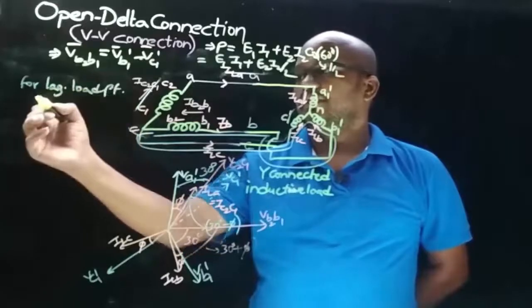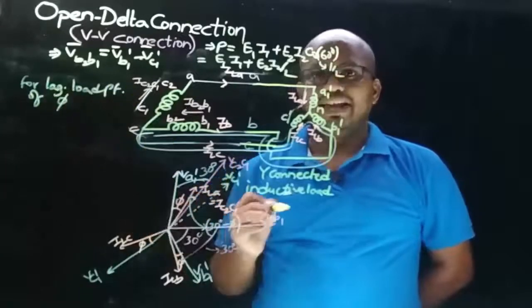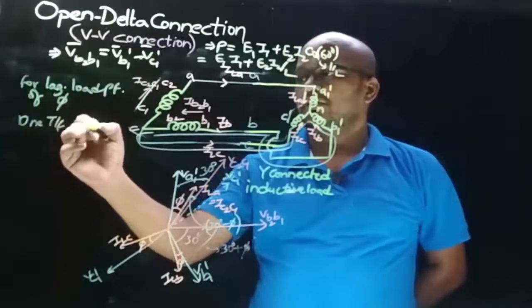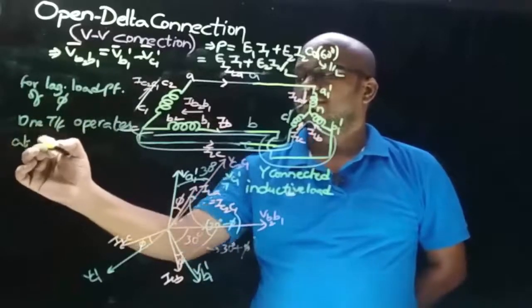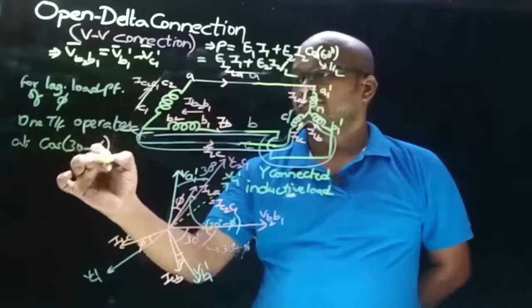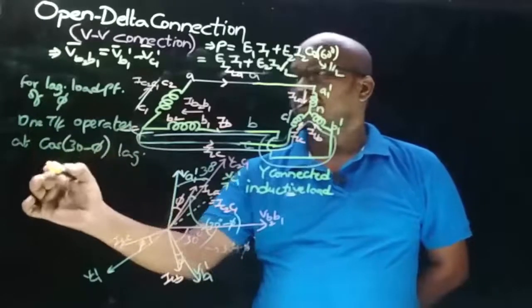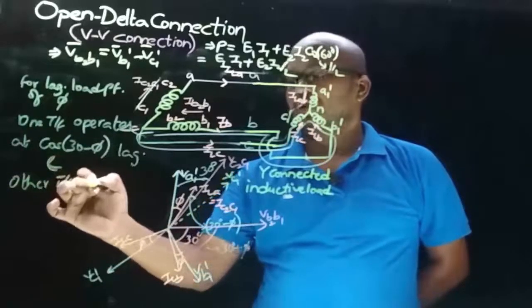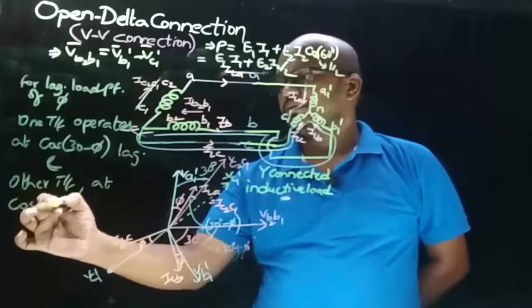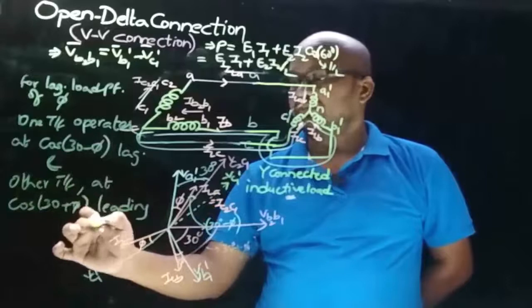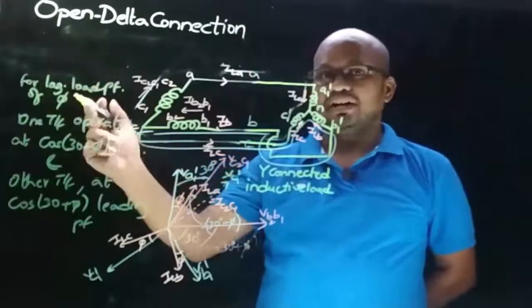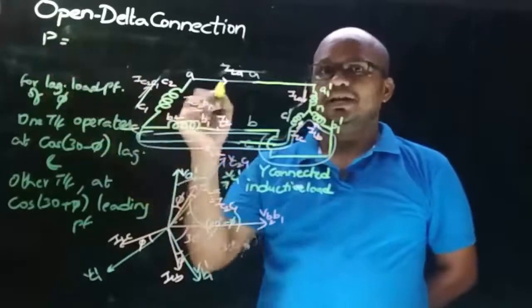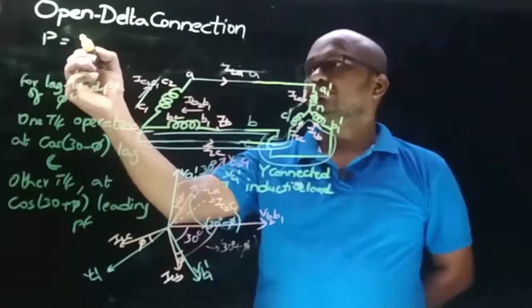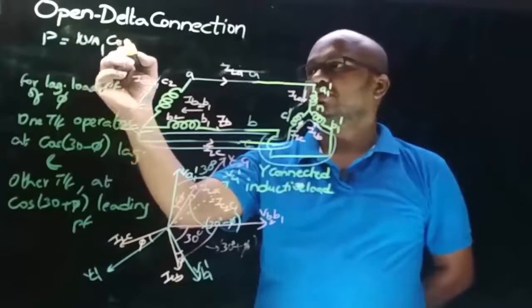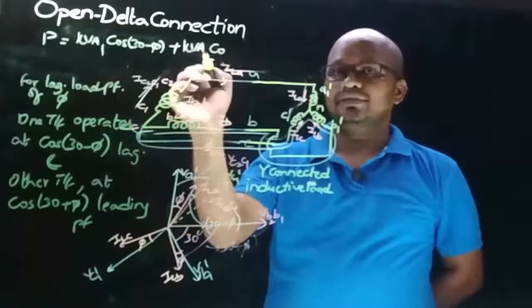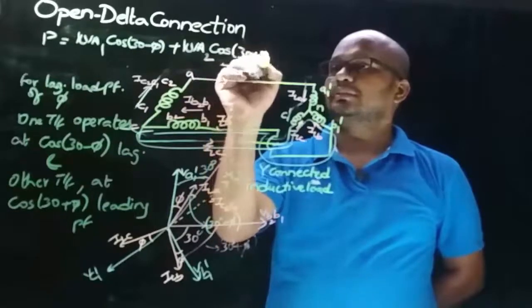which means that for a lagging load power factor of phi angle, one transformer operates at cos 30 minus phi lagging, and the other transformer operates at cos 30 plus phi leading power factor. Therefore, for a lagging power factor angle of phi, the total power supplied by the open delta connection to the load is P is equal to kVA of one transformer into cos 30 minus phi plus kVA of other transformer into cos 30 plus phi.